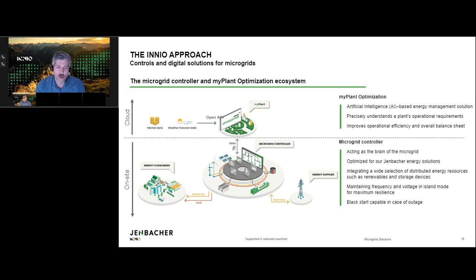So as long as the microgrid is grid connected, myPlant optimization can optimize the plant. As soon as there's an outage, it seamlessly transitions into island mode operation, and the microgrid controller takes over again, ensuring stable operation in island mode.